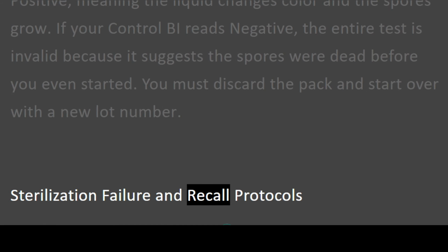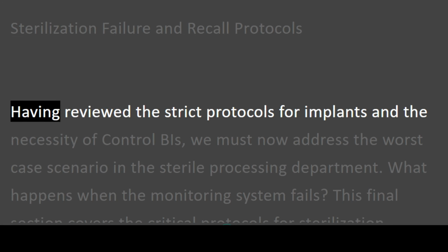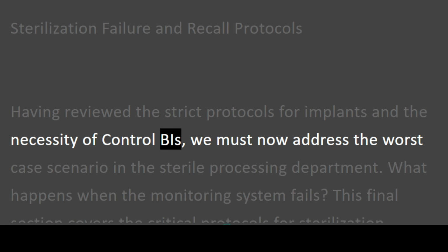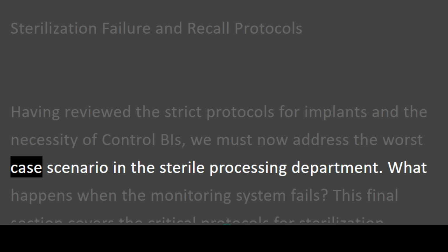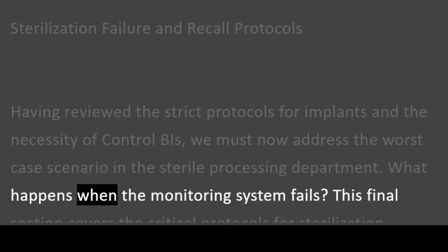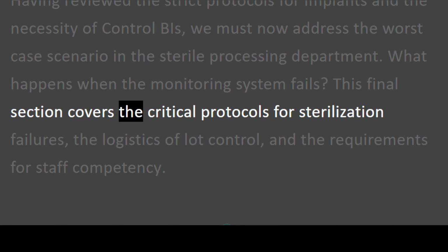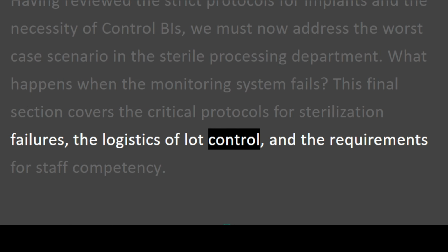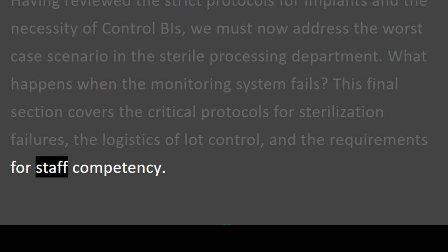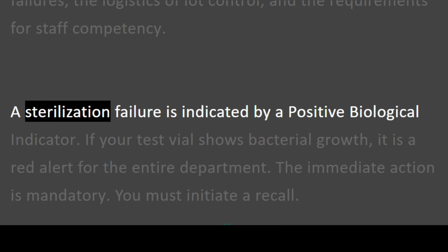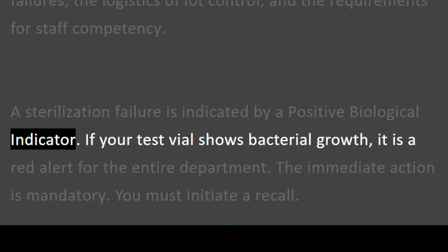Sterilization failure and recall protocols. Having reviewed the strict protocols for implants and the necessity of control BIs, we must now address the worst-case scenario in the sterile processing department. What happens when the monitoring system fails? This final section covers the critical protocols for sterilization failures, the logistics of lot control, and the requirements for staff competency. A sterilization failure is indicated by a positive biological indicator.